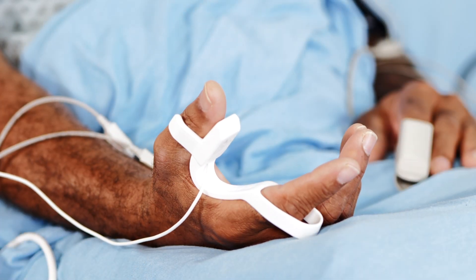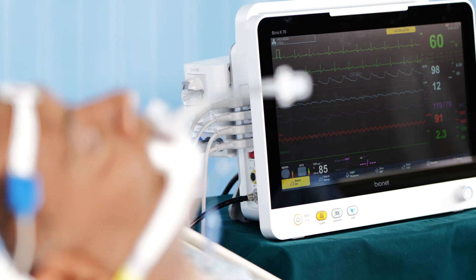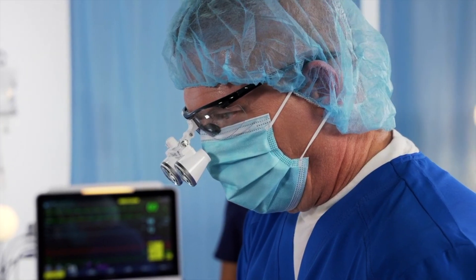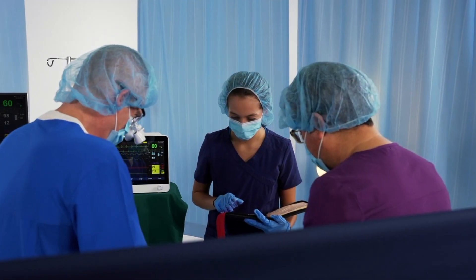With a precise indication of the impulse transfer between the nerve and muscle, NMT can be blocked efficiently by neuromuscular blocking agents during endotracheal intubation. The simple yet quantitative interface turns difficult and complicated workflow into clear and recognizable data for users during the procedure.